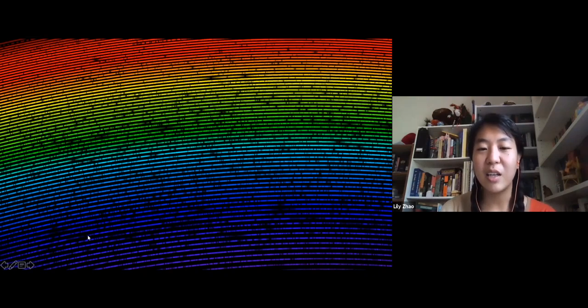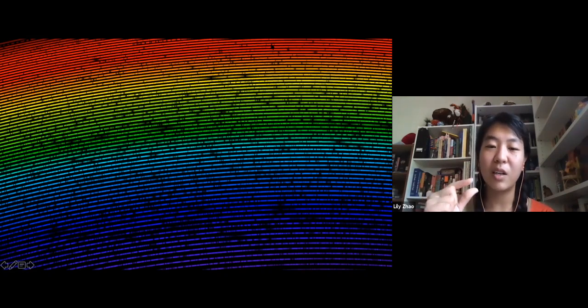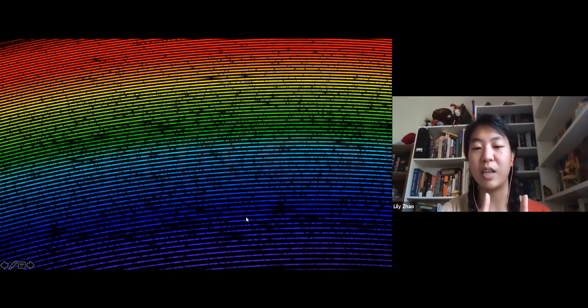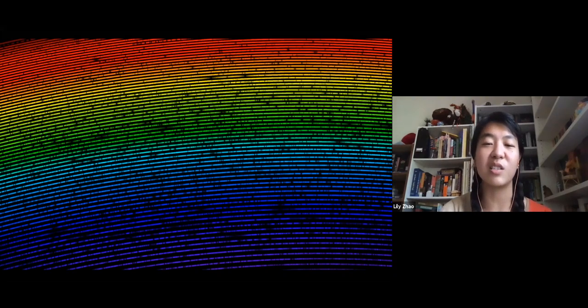You'll notice that each one has a bit of a curve to it. Also, the echelle orders down here are more spaced out than up in the red, where they're closer together. That also describes how the wavelength gets dispersed throughout the spectrograph. So here, the difference between one pixel to the next will be wider than over here, where one pixel to the next will have a smaller wavelength difference. These are all sorts of things you have to take into consideration when trying to assign the wavelength, or the color, of each pixel.